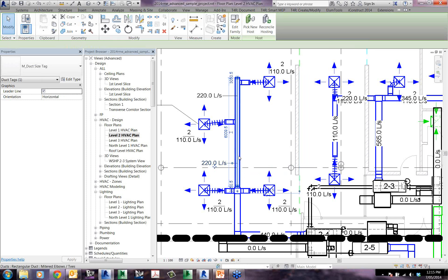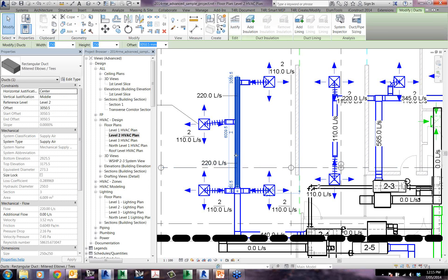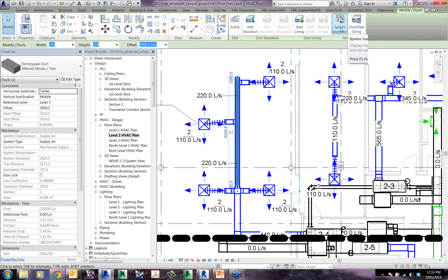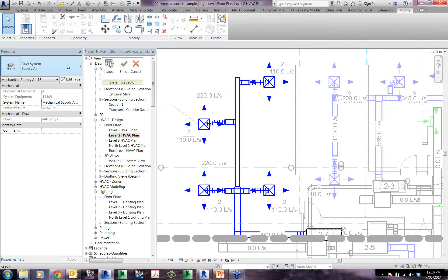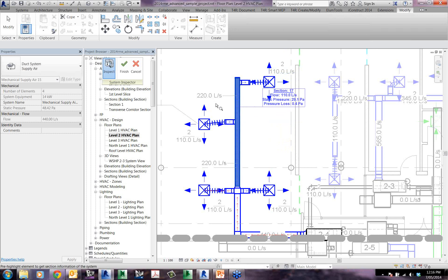In 2014 and earlier, the flow — for example the litres per second being displayed from a section of duct — is obviously being calculated for those two diffusers or air grills. If you come up past a tap, realistically you should see a drop, but the tag is still showing 220. Using the system inspector tool in 2014, it would actually show the correct values — 220 there, and then 110 past the branch — but it still wouldn't tag accurately. That was the issue: you couldn't tag these accurately.